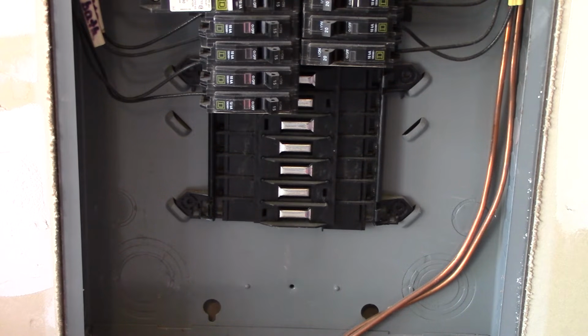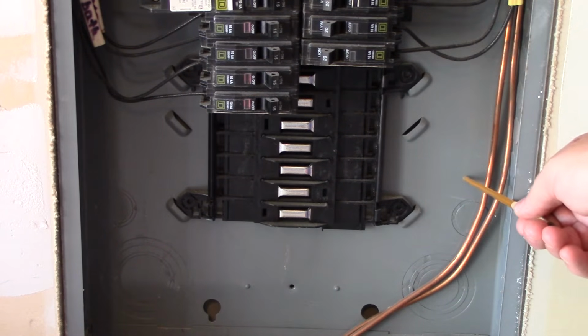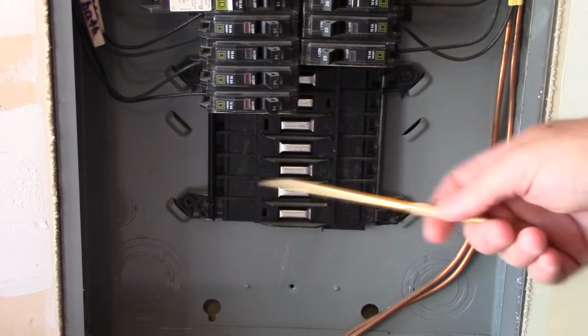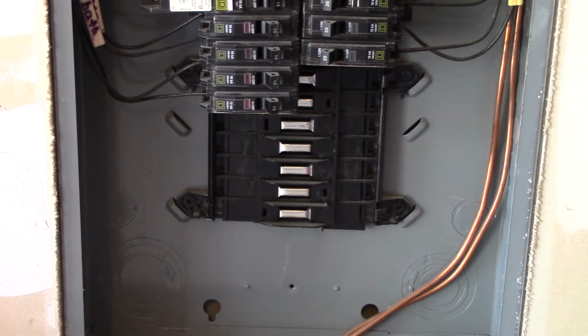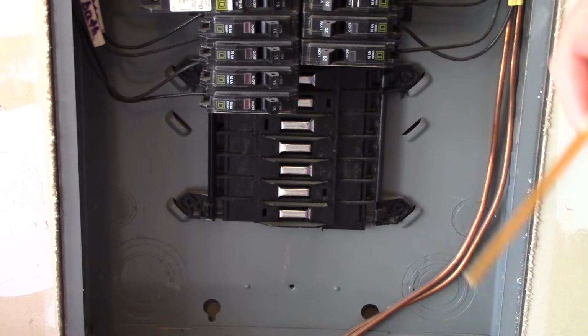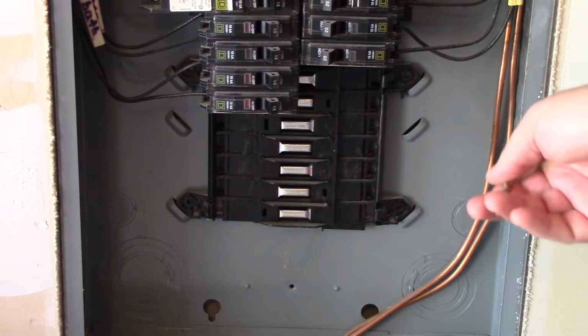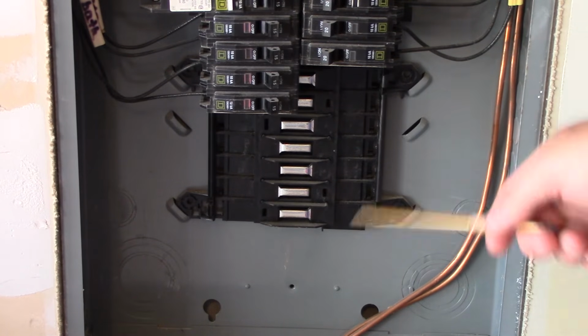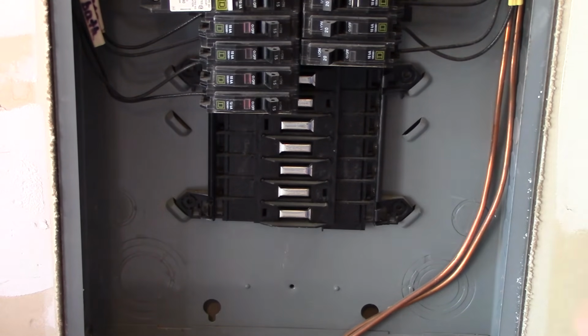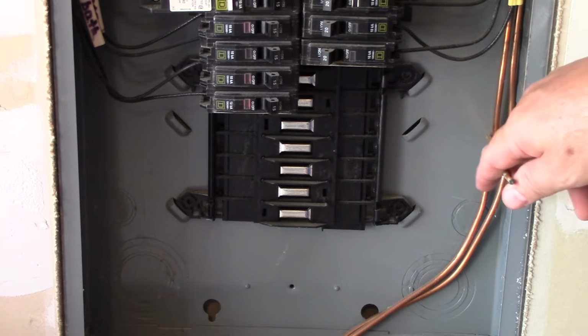But there is what's called a Ufer ground, or a concrete encased electrode ground, here on this dwelling, which in this case they ran a 4-gauge copper to that location, which is in accordance with 250.66, and you have an A, a B, and a C, which gives you some allowances for ground rings, concrete encased electrodes, and ground rods, plates, and pipe electrodes. We have some allowances there, and so for a Ufer ground, or a concrete encased electrode, it doesn't have to be any larger than a 4-gauge, in this case copper. All right, so that's what they ran. They chose to run copper to that.